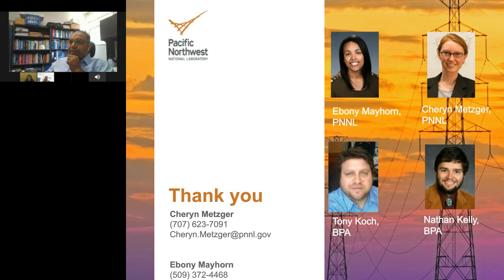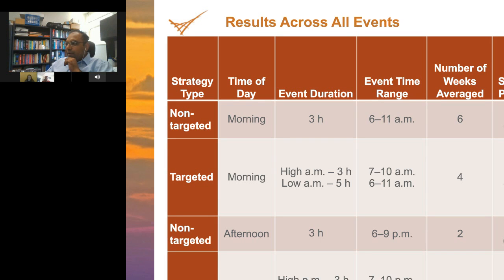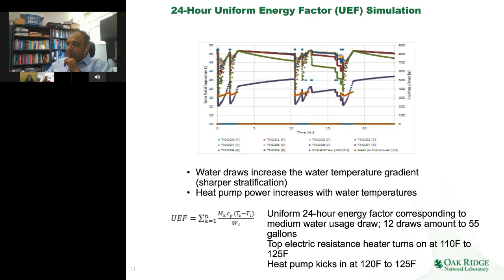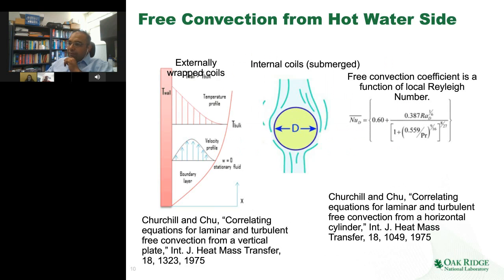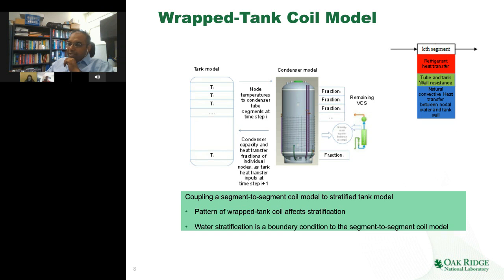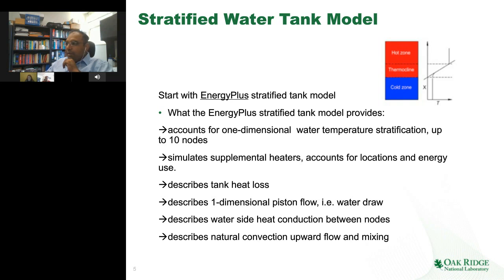I did show one summary slide where we were basically looking at the overall performance of various working fluids. And that obviously was not really discussed in detail, but if I may go back, I can show you a summary slide, which I think has two different refrigerants which are not discussed in detail, R450A and R513A. They also performed really well, because if you look at the composition, they are blends of HFOs. They have about 40 to 50% R134A. But their properties are fairly comparable, and so was their performance.